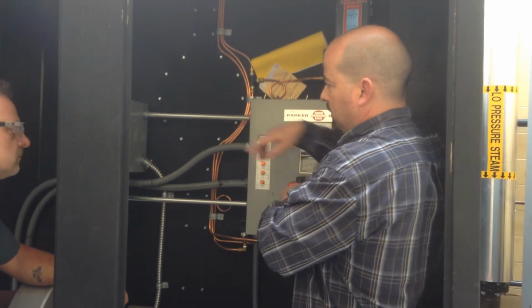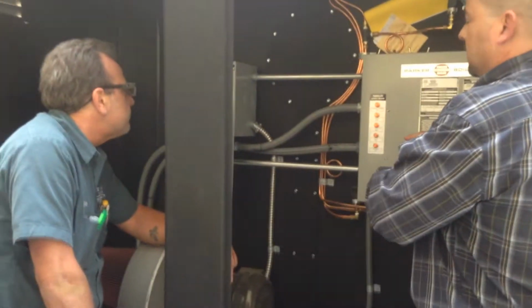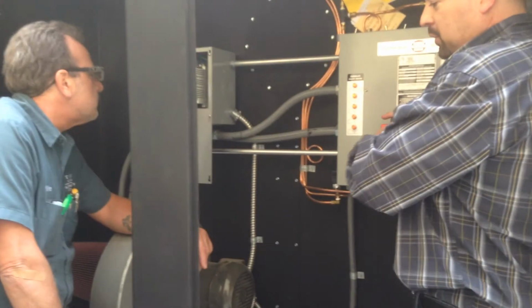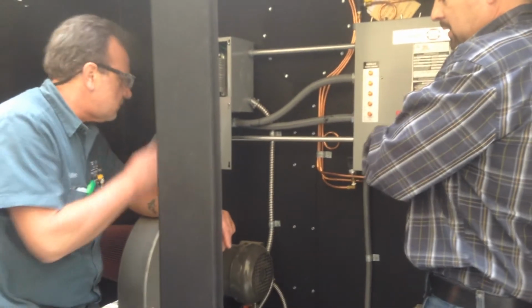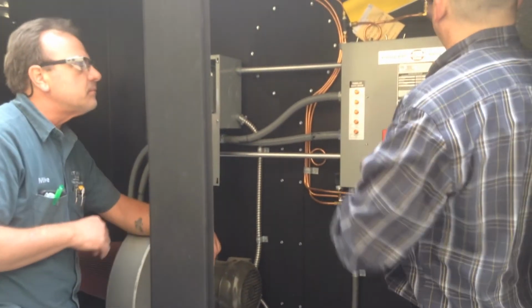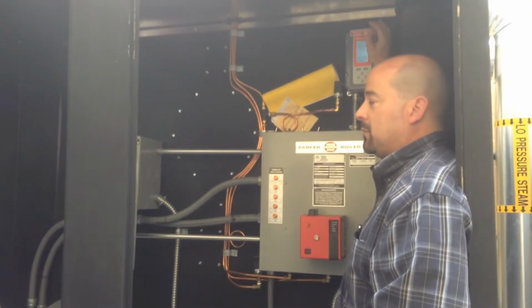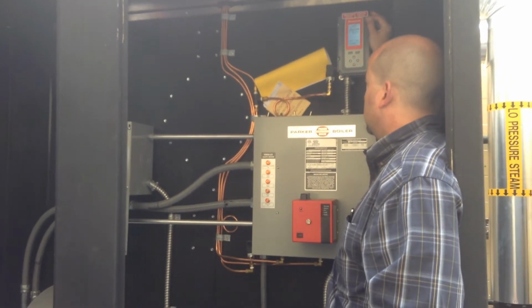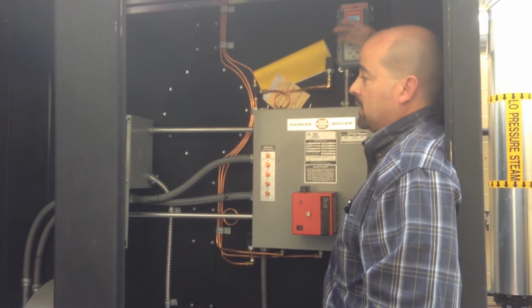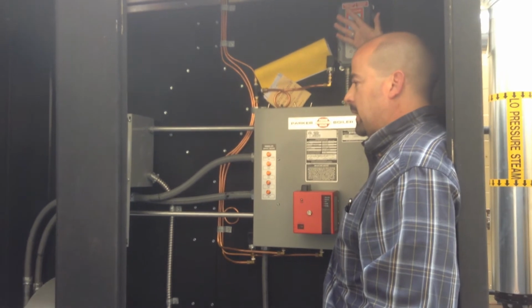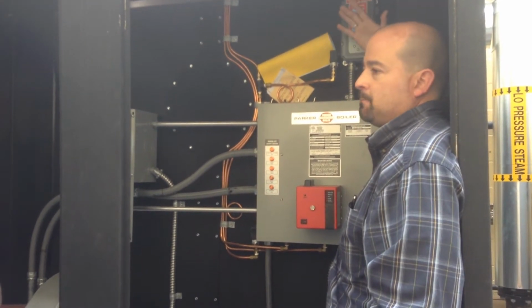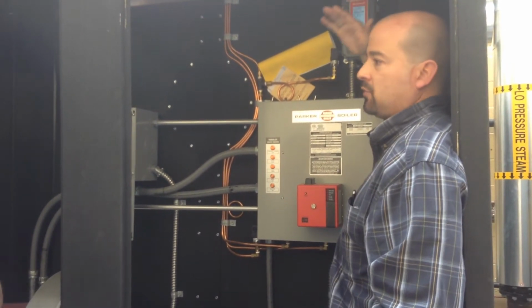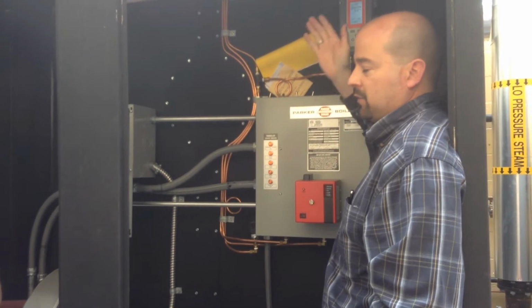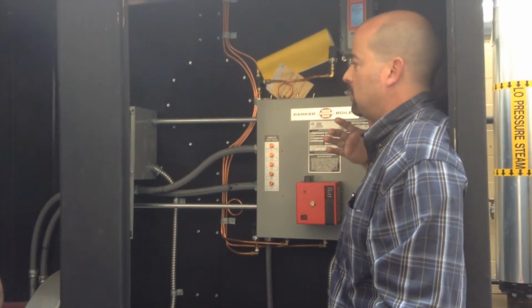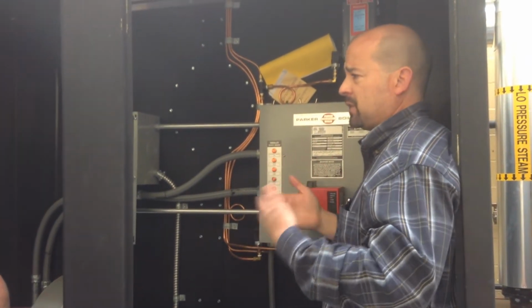And then this is a variable frequency drive. So this boiler is full modulation. The Honeywell T775 monitors the steam pressure in the boiler. And we tell it, okay, we want you to turn off at 10 psi, but let's say at 7 psi, we want you to start driving down into low fire. Fully adjustable. We could say at 5 psi, whatever you want, in order to avoid short cycling.